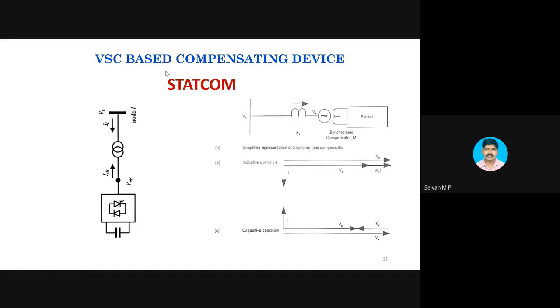Of course, you can have a resistance also. Why don't we have resistance? Because with resistance, there will be a power loss. So we will not prefer resistance. We will prefer reactance. Definitely that reactance also will have a certain amount of resistance, so there will be a power loss. Of course, we have to calculate that power loss also and take it into consideration when you design the components. For analysis, we neglect that and treat it as a resistance-less reactance. Okay, so without this reactance, STATCOM cannot work. STATCOM means not only this power electronic part, it includes this transformer also.